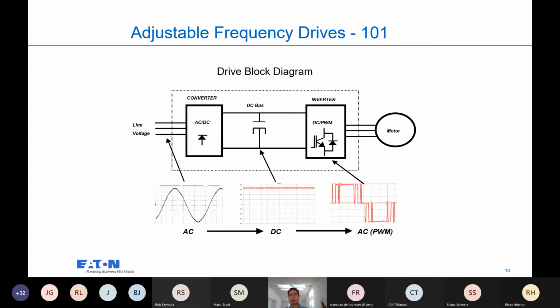Okay, for starters, let's go with a VFD. How does a VFD work? You have your three-phase power going into the converter section, onto a DC bus, and then through IGBTs, you create a pulse width modulated signal that recreates a power wave going into the motor. This pulse width modulated signal will have a frequency here. What's an IGBT? Insulated gate bipolar transistors. These are solid state devices that can help pulse onto the motor and recreate an AC power wave.